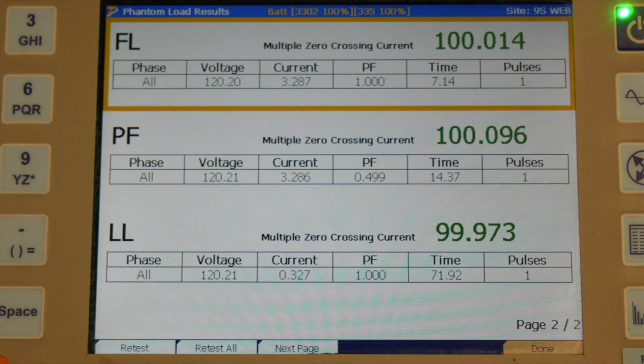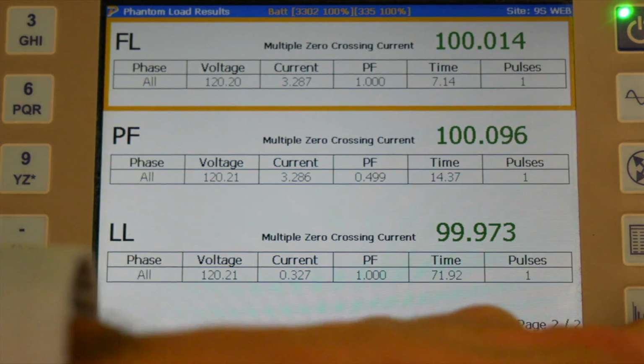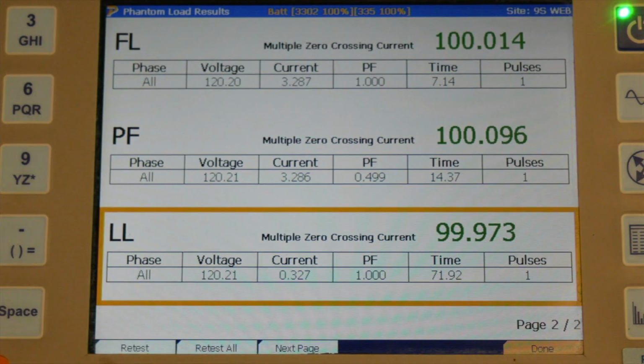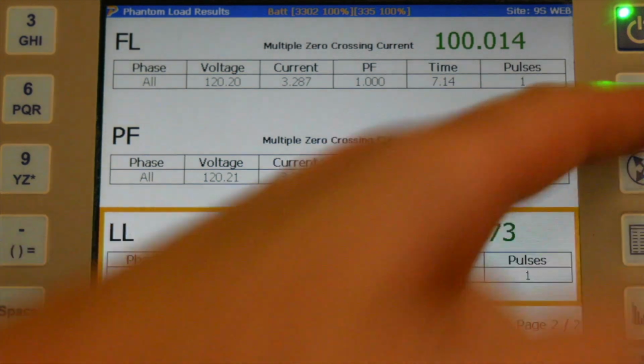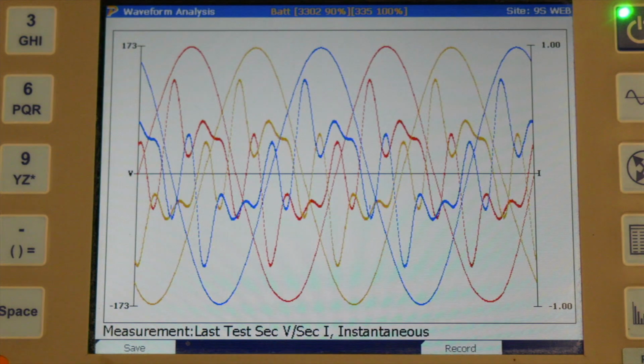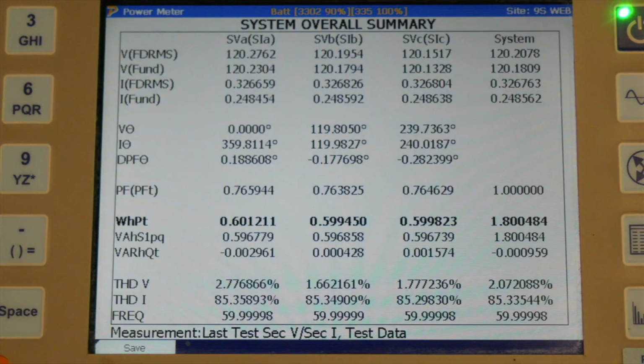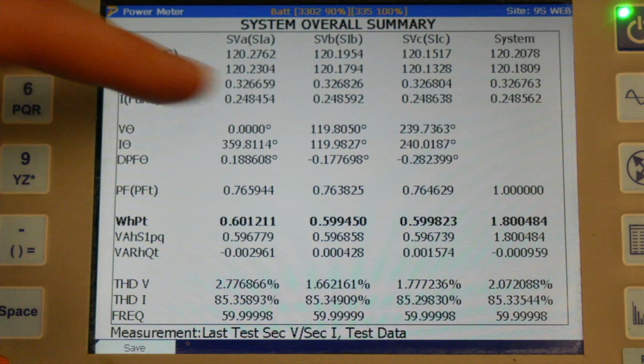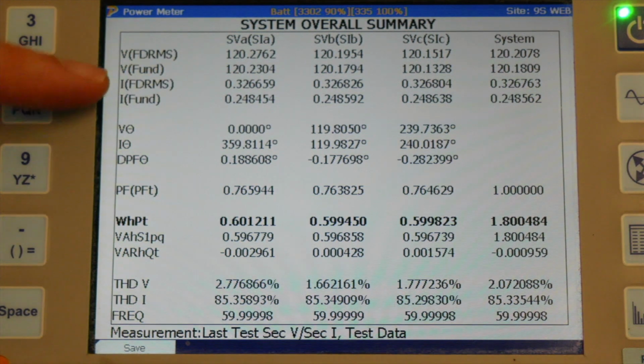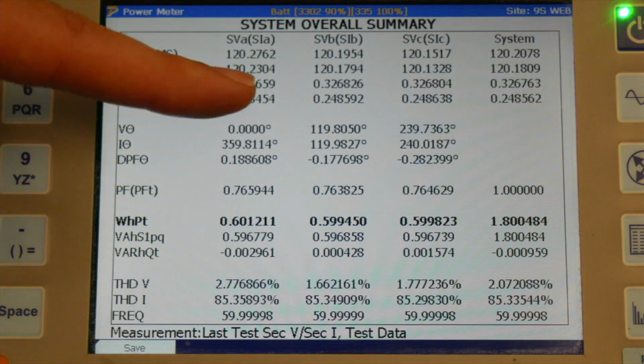So I'm going to show you. We also ran a test on the multiple zero crossing point, and I want to show you what the waveforms look like. At the end of the light load test, we actually save the data. If you look at the waveform screen, you can see how distorted that is. Notice your voltage is a sine wave, but your current is way out. Another interesting point is this was a light load test. I ran a 1/4 amp. The question I had is, notice these 2 fields here. One is fundamental and one is RMS. Steve, can you explain to me why these 2 numbers would be different?